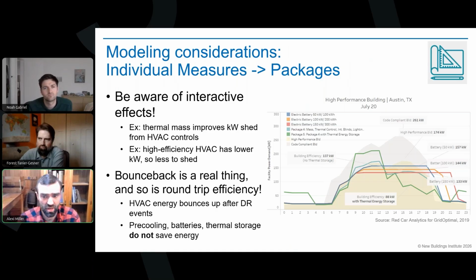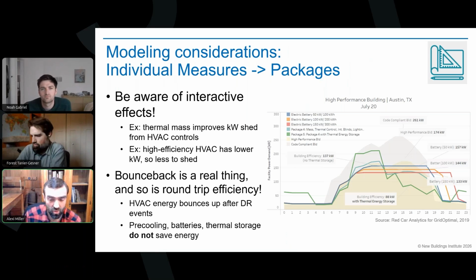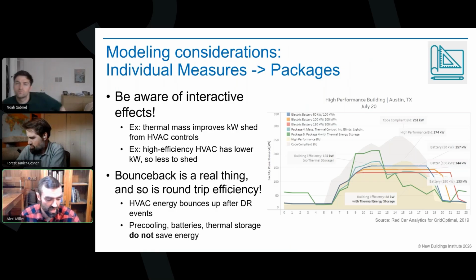I also want to note that bounce back exists if we model a demand response event by adjusting the schedules, say, of HVAC set points. Say it's a summer afternoon, we go from 72 to 74 degrees. When the event ends, we may see a bump in consumption of the mechanical system because now it's trying to get back to that 72. That may drive an increase in demand, and we don't want to set the demand by setting up that bounce back. It's just something to pay attention to in the model — are we potentially setting our demand charge through a bounce back effect or through a pre-cooling effect?